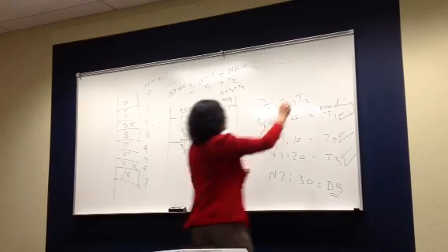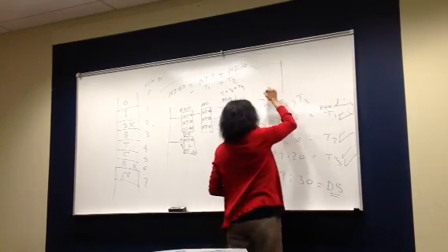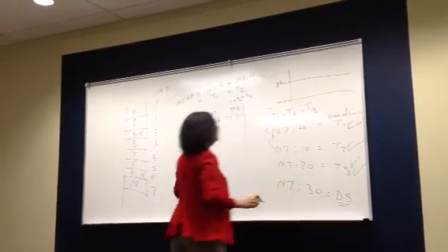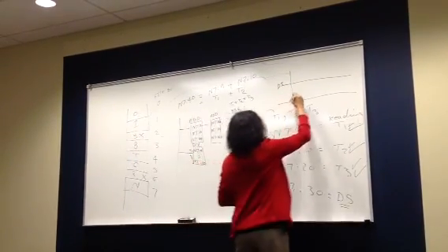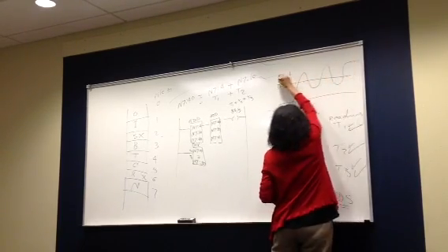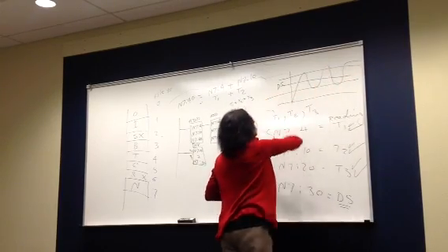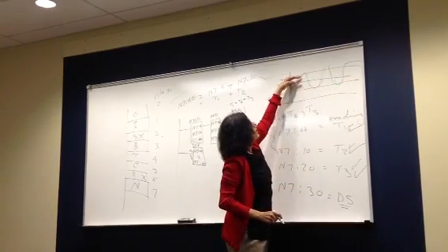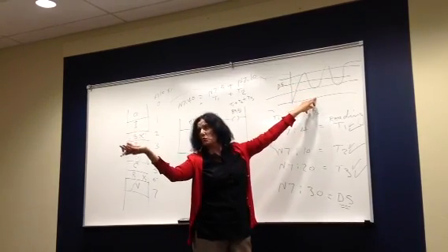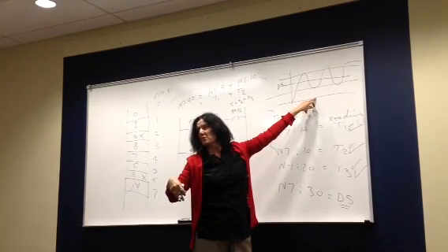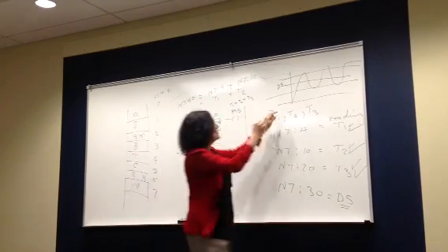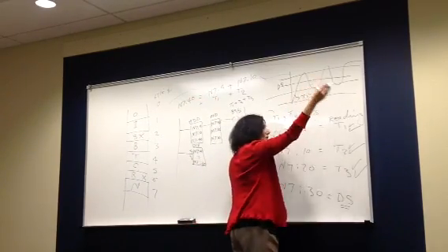I'll tell you quickly here. I have here the downstream water level, and then I get the threshold here. I go between that, and I take every transmitter. If I am above or below, I eliminate it. I take the average of the other 2, but that's going to take too long. So I take one by one and compare that. I have a dead band. I take transmitter 1 and I repeat it for 2 and 3.